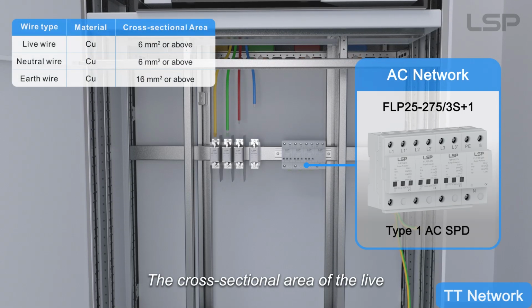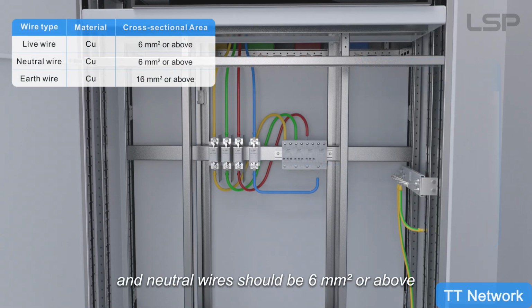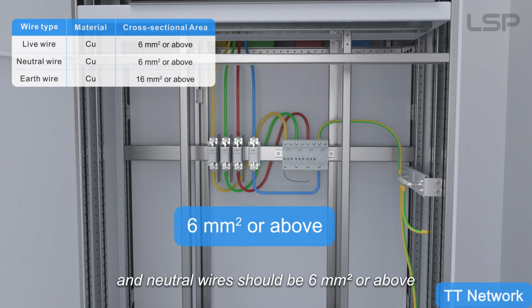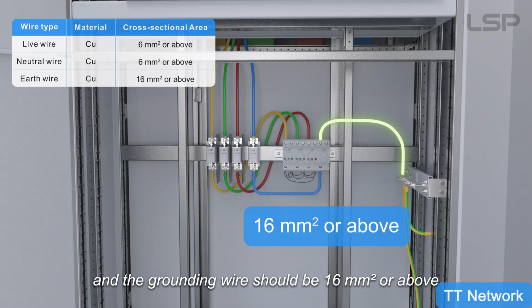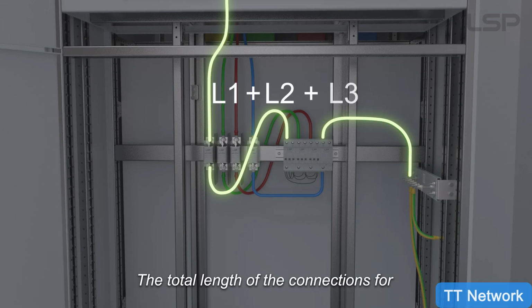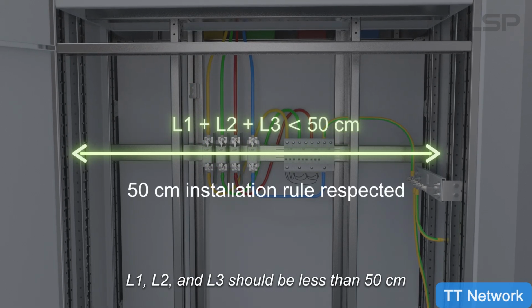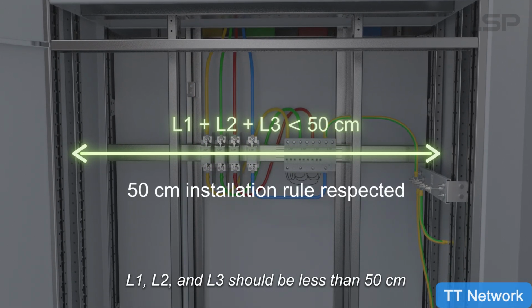The cross-sectional area of the live and neutral wires should be 6 mm² or above, and the grounding wire should be 16 mm² or above. The total length of the connections for L1, L2, and L3 should be less than 50 centimeters.